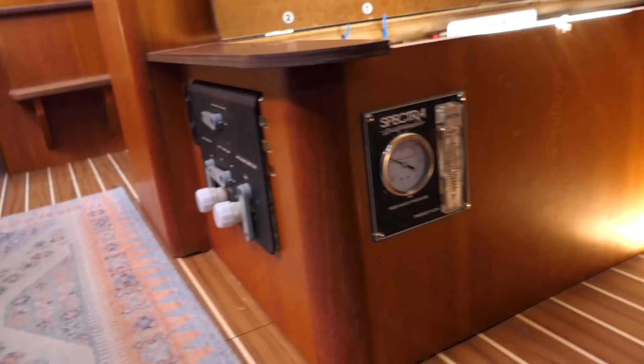In case you're wondering what I'm looking at, I don't know how well it'll show up on video—it's that little gauge that shows your gallons per hour or liters per hour. It's one of those things where the new pump head on the old pump now makes the previously good pump not look that great, but I don't really want to buy a whole other pump head for that one too. Once we replace the membrane, I bet that'll come up a little bit. Oh yeah, and I tested the water—it's still at 875, which is not good, but that's our mark. God, I hope we can beat that.